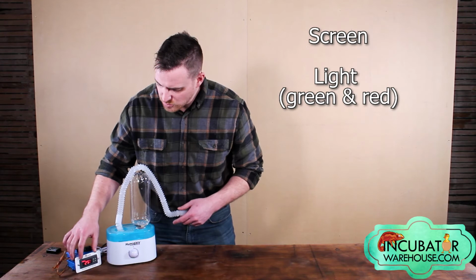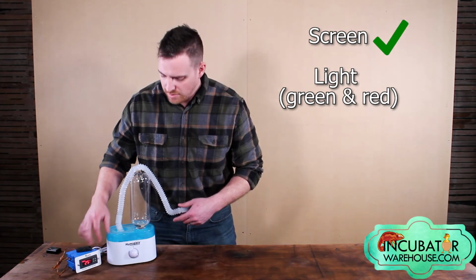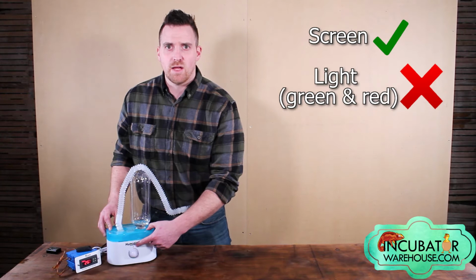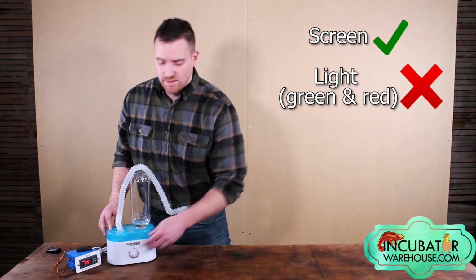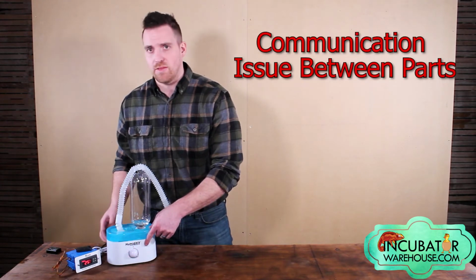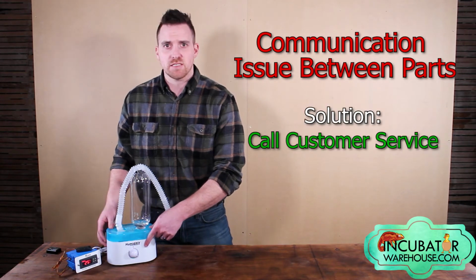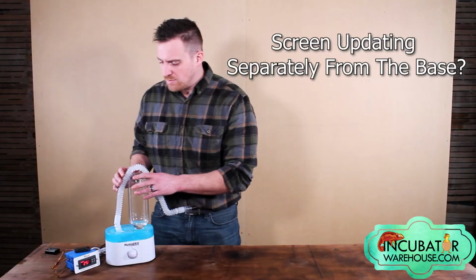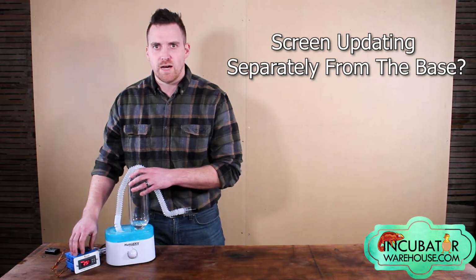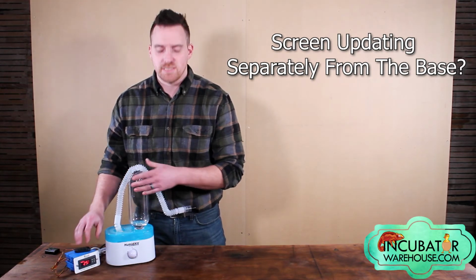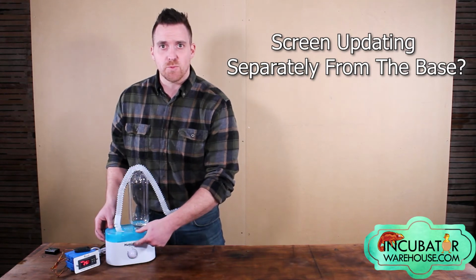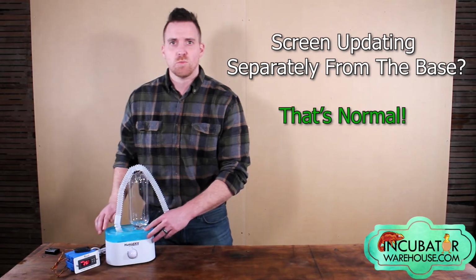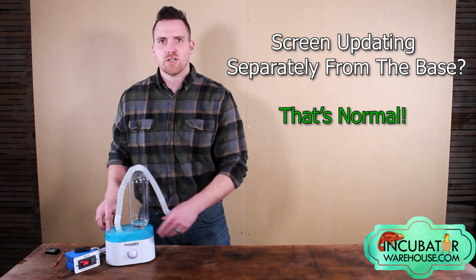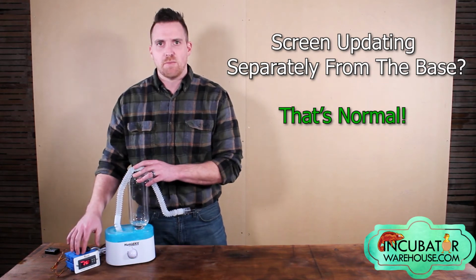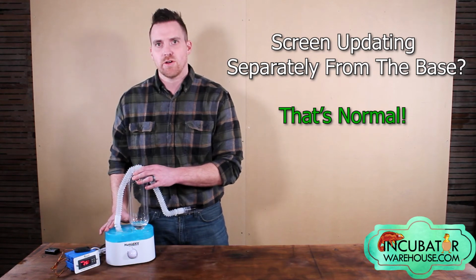Another problem you might encounter is the module will have the lit screen, but the Humidikit base will not have a green light or a work light. This is a problem between the module and the base and often needs to be resolved with our customer service agents. Now, sometimes you might notice that the module readout will continue to increase or decrease even after the Humidikit has either stopped working or started working. This is normal functionality. As the humidity increases in the incubator and it reaches the set point, the sensor will tell the Humidikit to turn off.